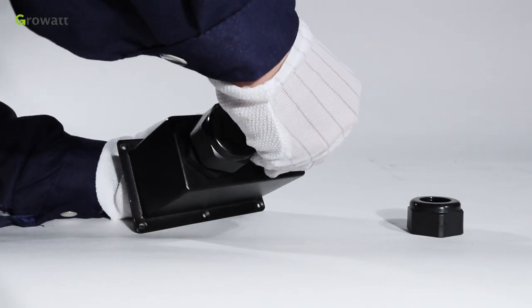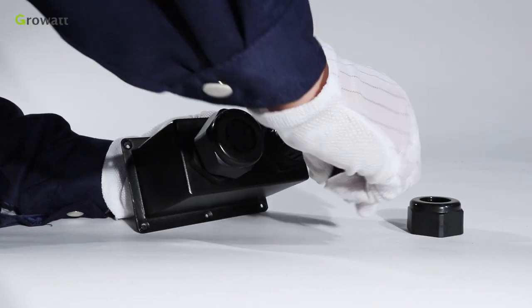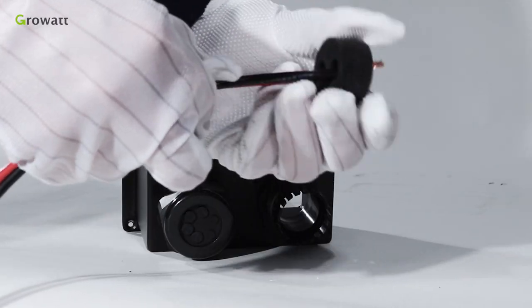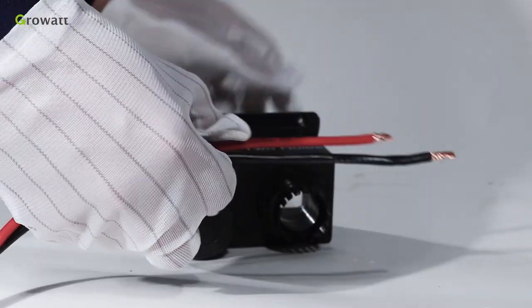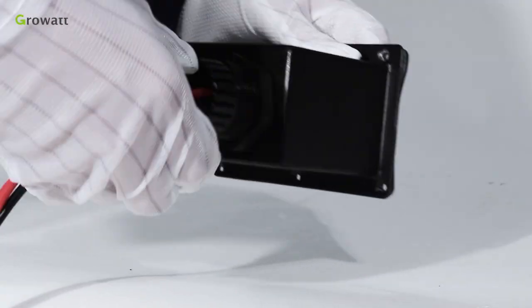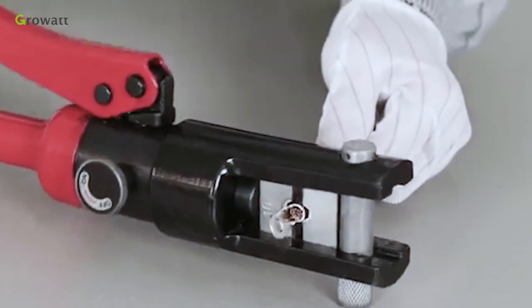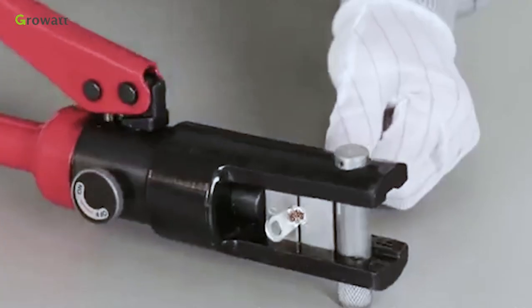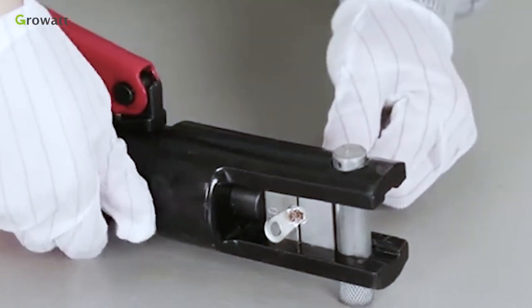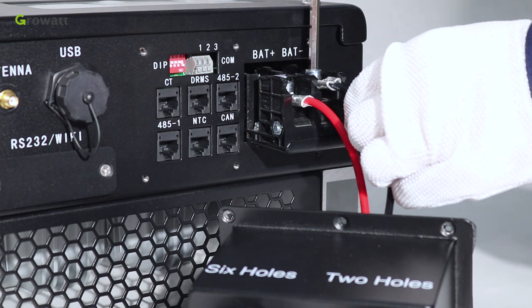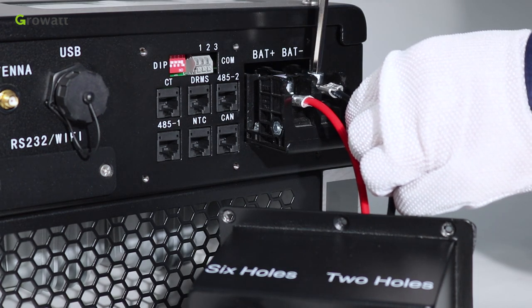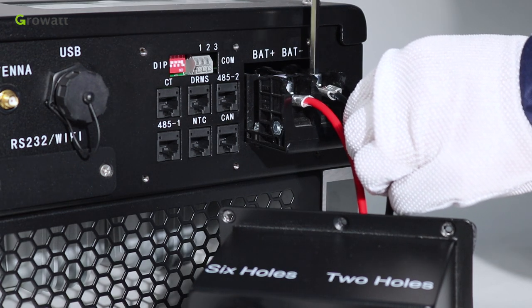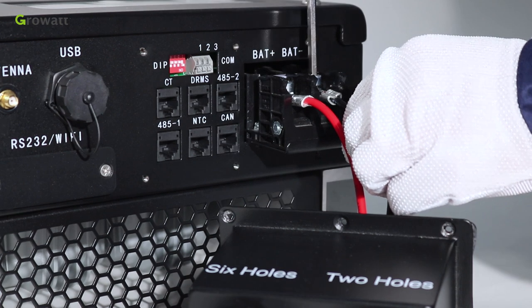Dismantle the waterproof cover, thread cables through a pressure screw, seal ring, threaded sleeve, waterproof cover. Thread cables into connection terminal, then press the terminal by relevant tools until the battery cables are firmly connected. Finally, connect positive and negative pole of battery cable to the respective battery terminal of SPH.